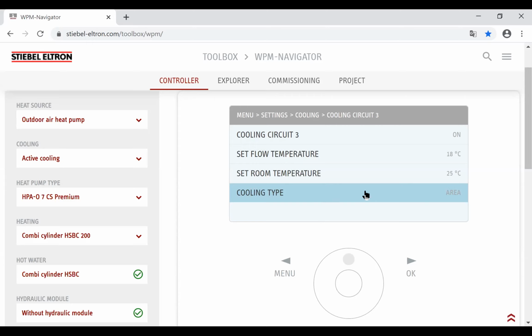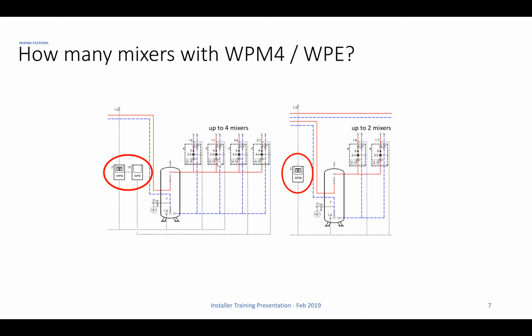So dew point manage mode means that the FET that's installed in that circuit, don't forget the FET would have to be inside the conditioned space. I know some people want to put FETs in cupboards and in laundries out the back or something like that. But if you're trying to do a dew point measurement, the FET needs to be in the conditioned space. The FET will measure the humidity, the FET will measure the room temperature, and the FET will make a dew point calculation. Then the set point for the water will be 2 degrees above the dew point.